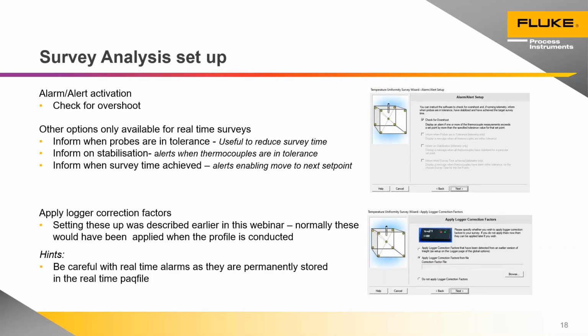We can set up the software to check for overshoots. When we have a survey file that's gone up to 1,000 degrees, an overshoot is not going to be easily visible to the eye on the graph, because it will be maybe 2 or 3 degrees, and the software will check for that automatically if you've checked the box.